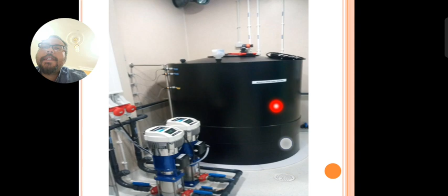The difference is the presence of a tank of treated water. In the ordinary water treatment unit there is a tank of treated water. But in the new water treatment units there is only a primary tank, no treated water tank, because the treated water tank is a negative factor for infection in the water treatment unit - it is considered a dead space for the growth of bacteria. Also, when machines begin to use water from this tank, air from the atmosphere enters the treated tank, and that air is not sterilized.